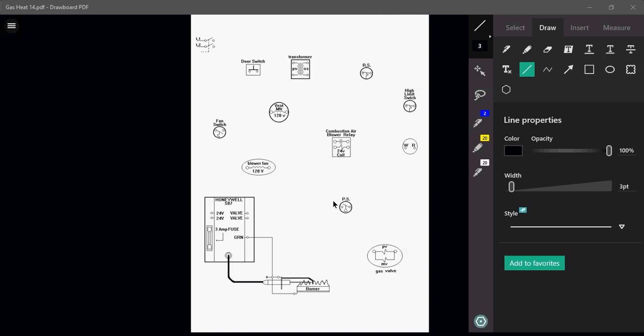So we have a door switch. The door switch, as I always like to call it, that's the dummy switch. That's really another safety in a gas furnace. The door switch has to be closed in order for electricity to flow through the rest of the circuit. Because we don't want Johnny Homeowner to start working on his furnace and then put his hands inside a blower wheel that's actually spinning at full RPMs. That's going to be a little bit dangerous. So the door switch is our very first line of defense when it comes to any sort of wiring on a furnace. In order for that furnace to work, the panels for the door or for the blower section of that furnace need to be in place.